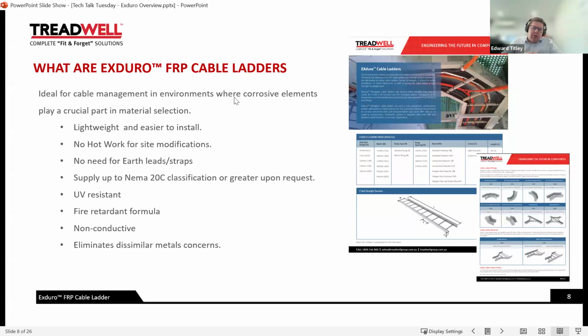A few advantages we mentioned earlier as to why I would consider an FRP cable ladder on my project. Number one is the lightweight aspect. It depends on whose brand of cable ladder it is, but typically we see a 20-30% reduction in weight, depending on whose product we're comparing to, whether it's mild steel, stainless, aluminium, etc. But there's typically a weight reduction. There's no hot work on site, so if we need to do any modifications, cutting or drilling, there's no hot work as part of that process. No earth leads or straps. Obviously, the product's non-conductive, so there's no earthing and bonding.